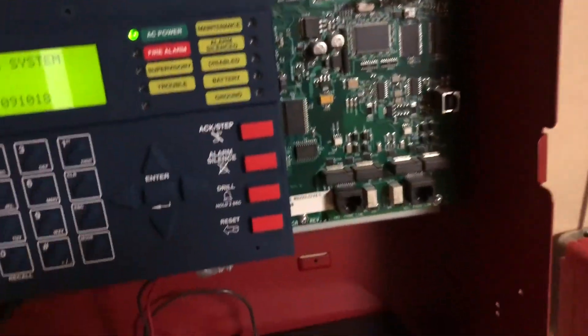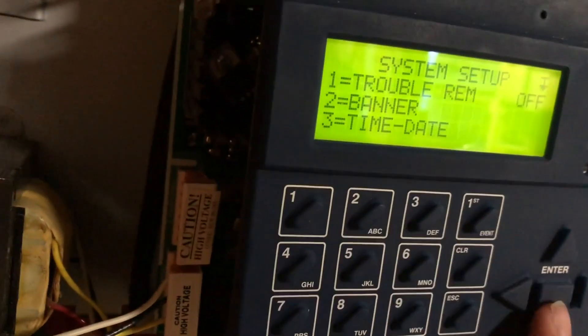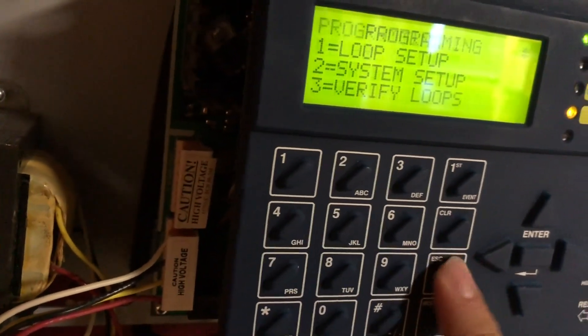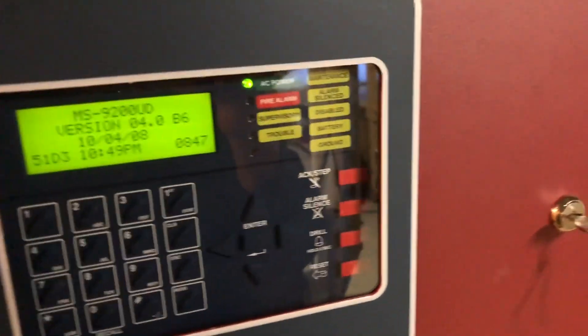We'll go ahead and reset. Guys, that's going to wrap up the video today. The test is so far inconclusive. I actually haven't tested yet to see if the older NHs sync and do temporal like this. I think it's unfortunate because there's this one very select city that I go to school in that requires continuous horns for no reason. It would be nice if they gave us that option the same way System Sensor does — System Sensor has nice little dials on the back to set it to continuous regardless. I've tried, had no success. Thanks for watching guys and I'll see you in the next video.